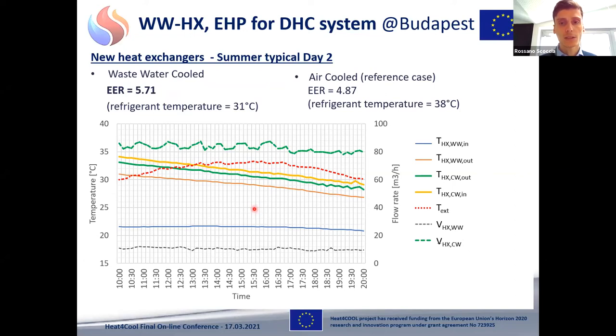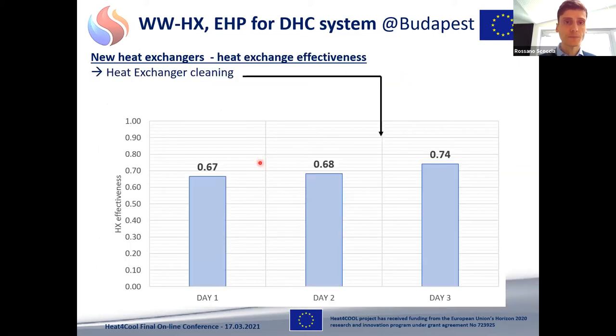While here in the charts, you see that the flow rate in this day of the wastewater was lower than the flow rate at the clean water side linked to the chiller. So for this reason, you see also that the delta T on the wastewater side is higher, between the blue line and the orange line, in comparison with the delta T on the other side, between the yellow and the green line. While the external temperature in Budapest, you see, in summer can be high, like 32 degrees C as shown in this day.